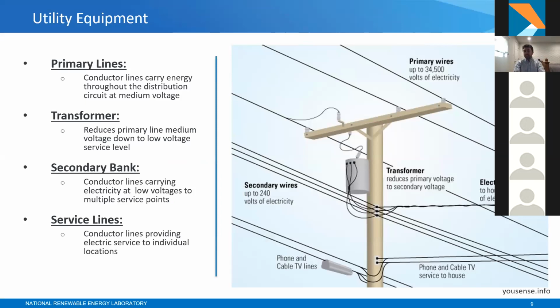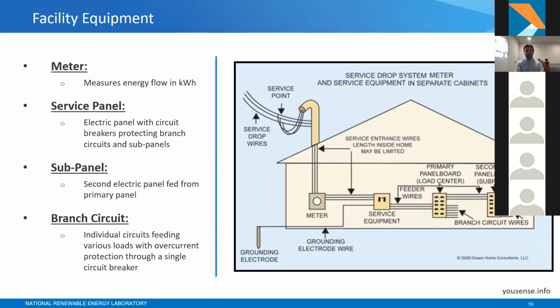And really the two key elements here that the facility is going to be considerate of is the transformer, making sure that it's rated large enough and sized large enough to supply this new load and there's enough capacity available. And then the service lines won't be overduty or overburdened with this additional load, because you'd imagine with new electrical devices coming online, you'll probably be consuming more current. Next slide.